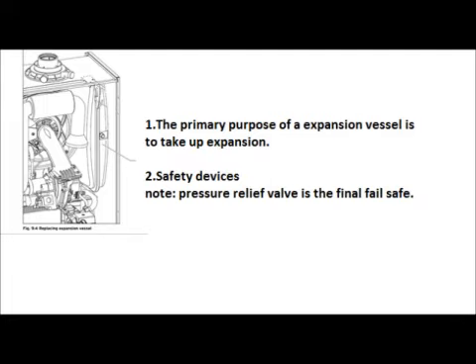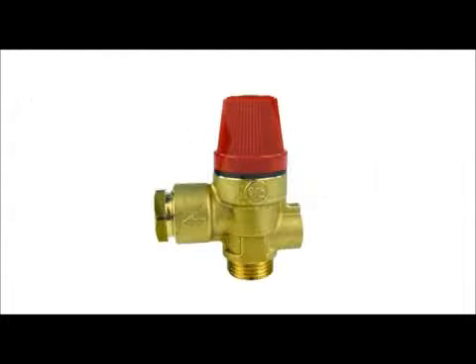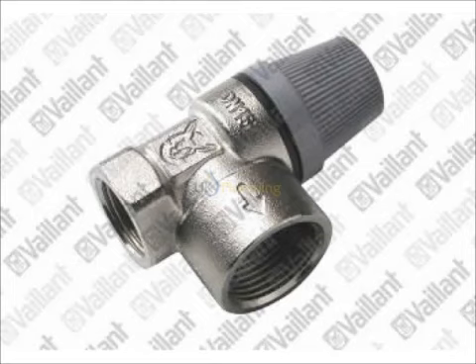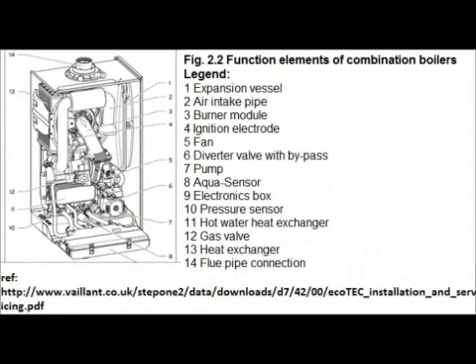Just in case that should fail — say, for example, the tube became blocked or broke internally or something of that nature — there's a secondary safety device to ensure the customer's safety is always maintained. That safety device is called a pressure relief valve. What it does: if the pressure inside the boiler gets to approximately 3 or 4 bar, it basically discharges the water. So instead of it exploding and making a big mess with water all over the place, it just pushes the water outside to keep everybody safe. As simple as that — that's what an expansion vessel does, and that's what the pressure relief valve does. They work together to ensure safety.